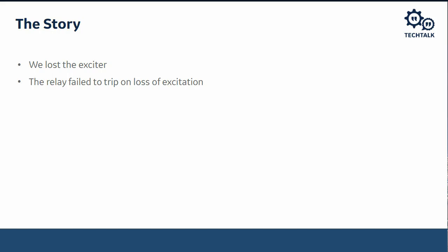So this problem may have existed the entire time this G30's been in service, or it may have developed recently. We don't know the answer to that. So how can I isolate the problem to as small an area as possible? Well, let's start looking at the actual event. So let's take a look at the oscillography.